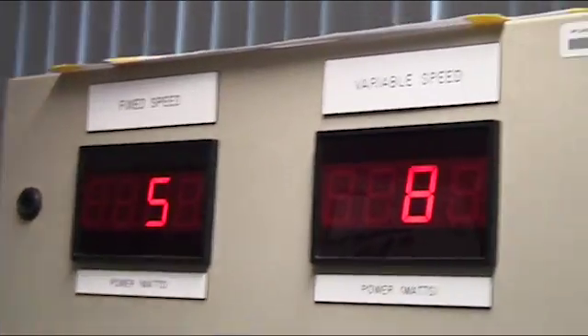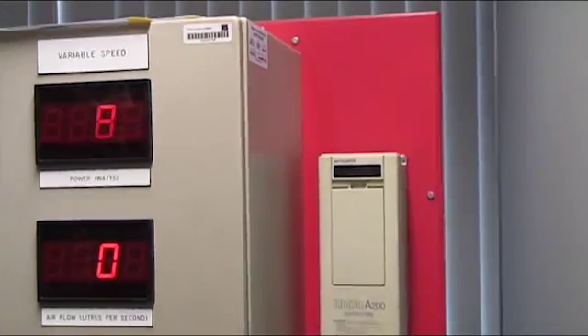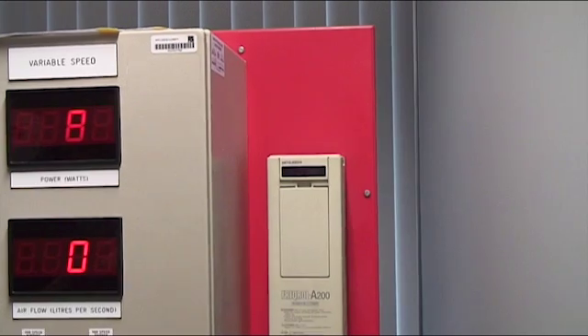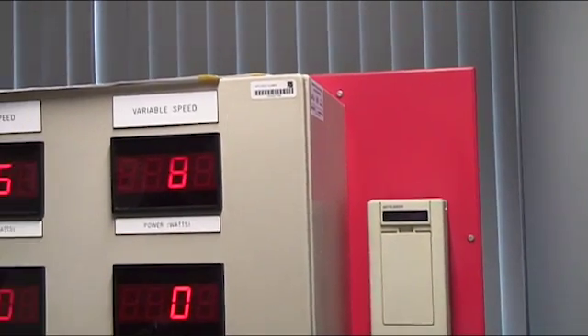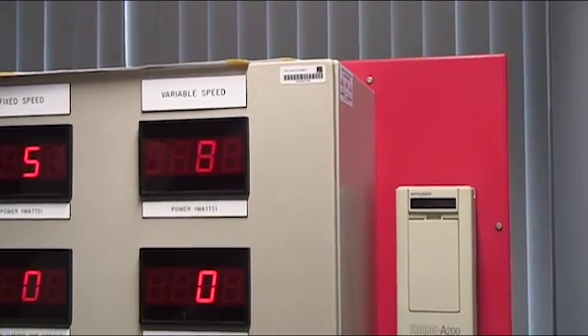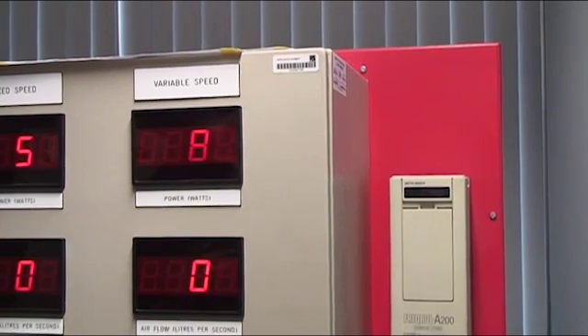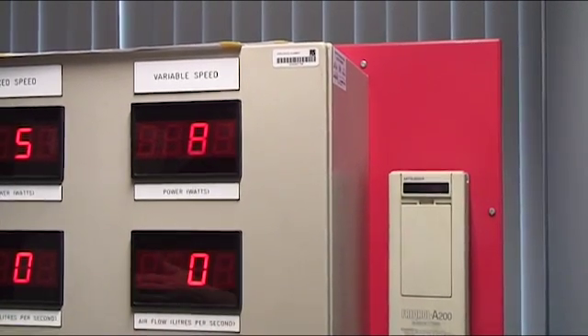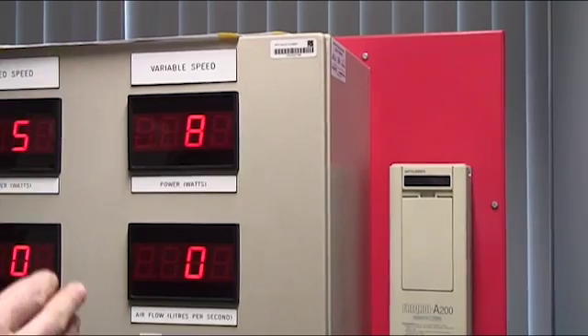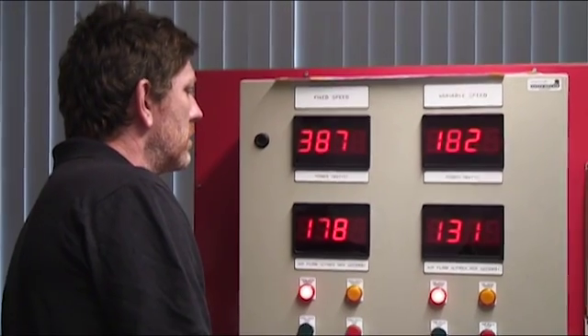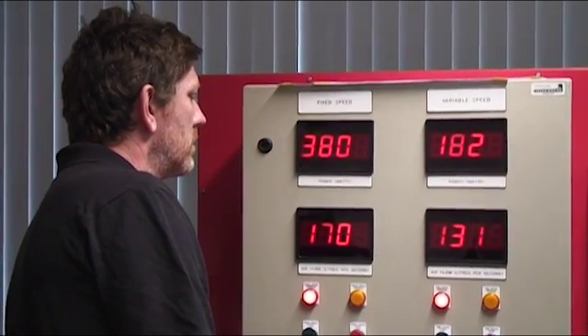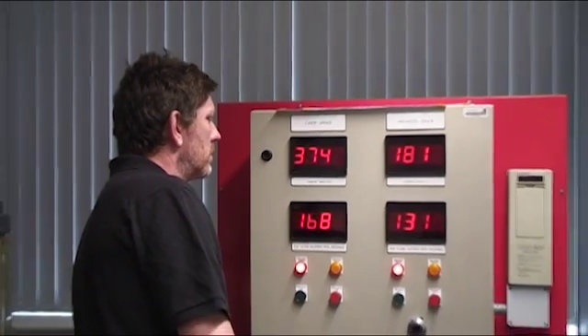On the right hand side, we have another fan that's controlled by an inverter. An inverter is an electrical device that controls the motor speed for the fan to deliver as much air as you want, so there's no waste in the energy. So rather than having a paddle like the system on the left, you want less air, you just turn the fan down. If you turn a fan speed down by 20%, your potential energy savings are just over 50% on a perfect system.